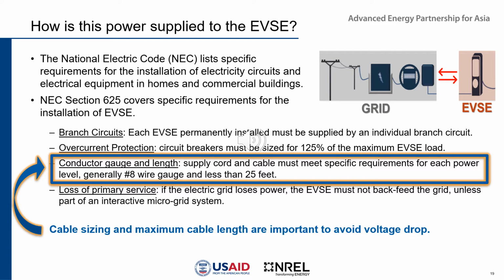That overcurrent protection in the circuit breaker must be sized for 125% of the maximum EVSE load. Take, for instance, an EVSE that's designed to supply 32 amps to the vehicle. The circuit breaker must be sized to protect 40 amps in accordance with the NEC requirements. In addition, the conductor gauge and length typically have guidelines on their sizing and maximum distance from the service panel to the EVSE. For instance, level 2 generally accepts number 8 wire gauge and less than 25 feet as sufficient to avoid excessive voltage drop.